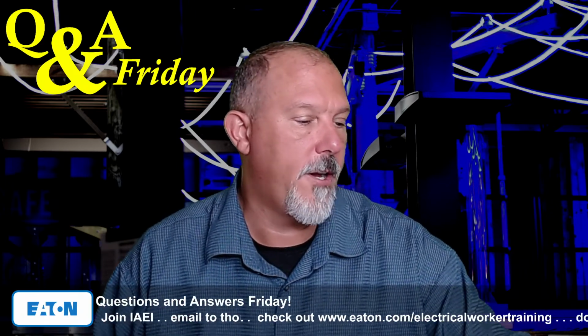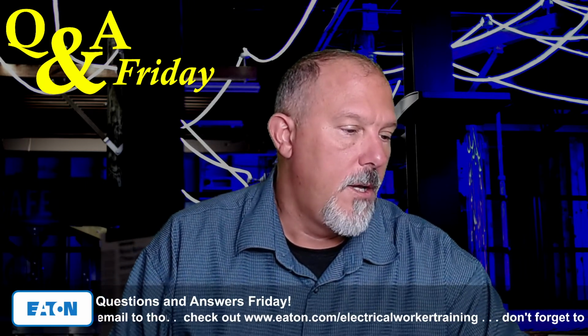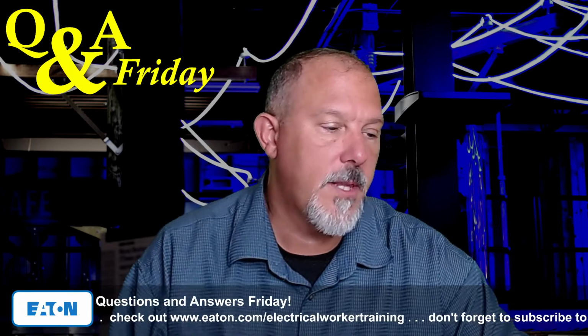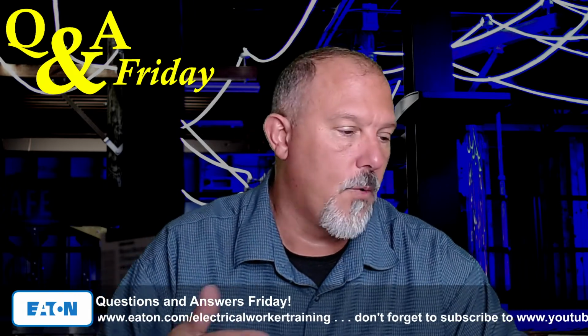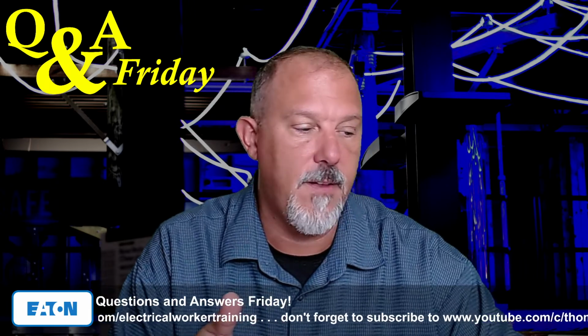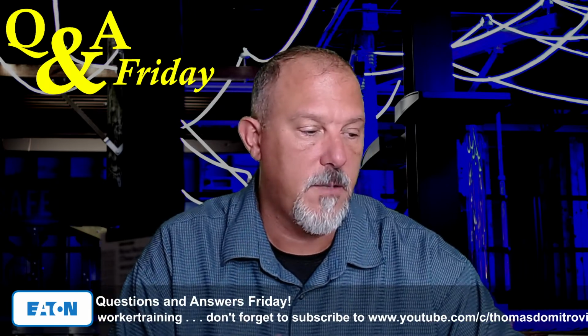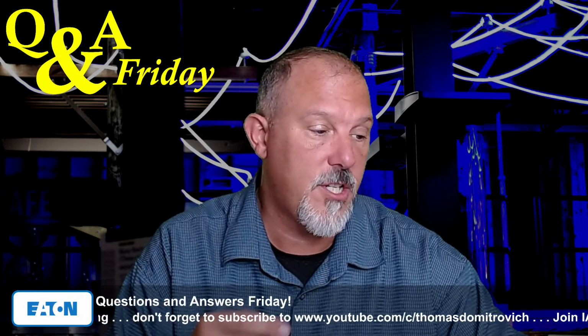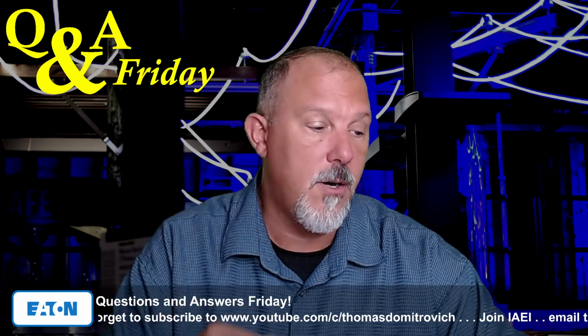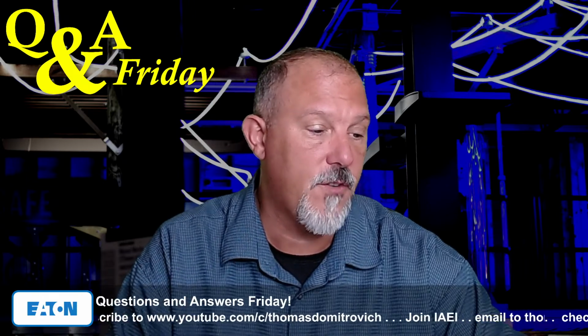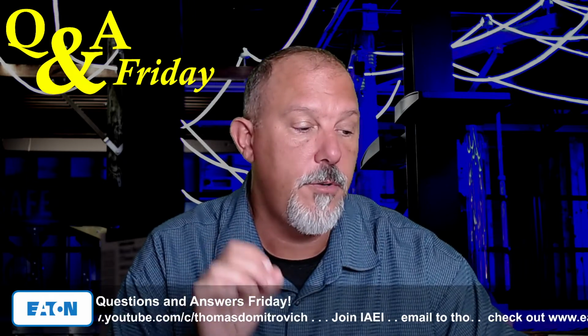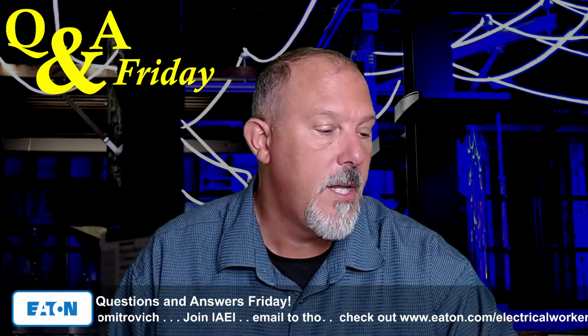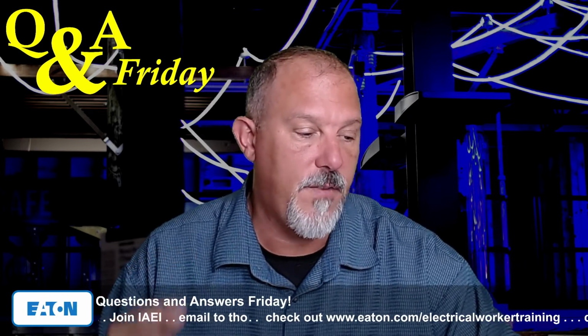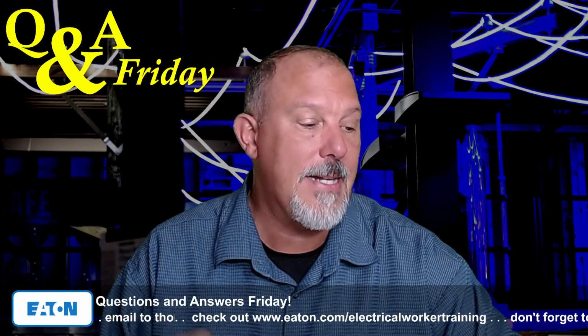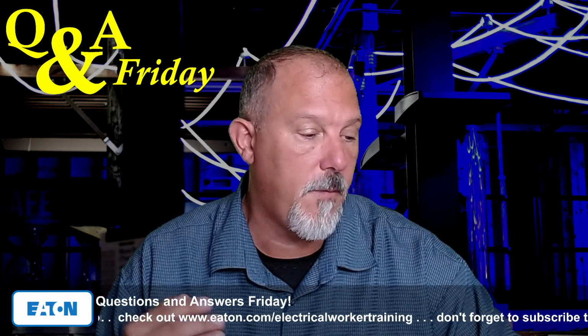Still trying to wrap my head around arc energy reduction. What is it appropriate to look for it during the plan review stage, at the inspection, or both? He has plans where the applicable overcurrent protective devices appear to indicate LSI, which translates into long time, short time, and instantaneous. For certain applications, it would include G at the end, which would mean ground fault, which would meet your 230.95 requirements. Does the instantaneous indication provide what I need, LSI in its entirety, or do I need more information?